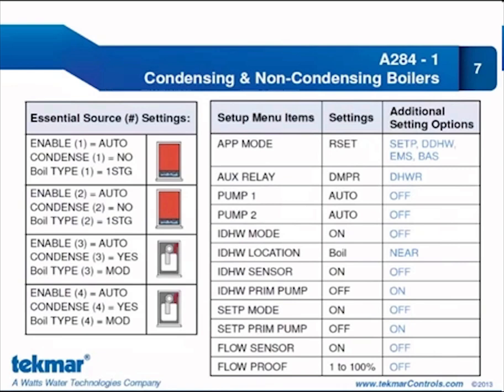Now you'll see a bunch of IDHW settings, and this is because we have made a move away from the mode settings that you're familiar with in previous controls. Mode settings are not overly intuitive, so you would have to refer to a manual to understand which mode you should be in. We wanted to make the 284 simple, so what we did is we took away those modes, and in this case you will specify, do you want domestic hot water? And if so, tell us some information about how it is piped.